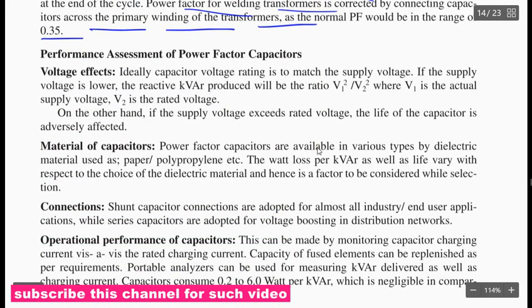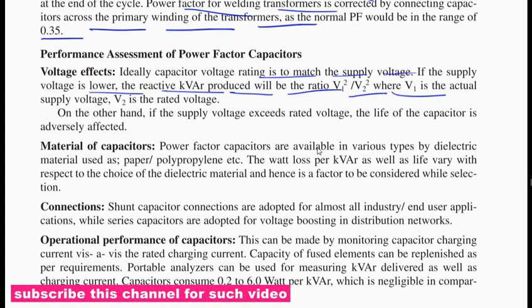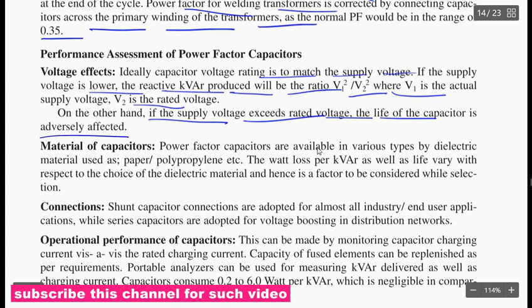Performance assessment of power factor capacitor. Voltage effect. Ideally, the capacitor voltage rating is the same as the capacitor supply voltage. If the supply voltage is lower, the reactive kVAR produced will be in the ratio of V1 squared divided by V2 squared, where V1 is the actual supply voltage and V2 is the rated voltage. On the other hand, if the supply voltage exceeds the rated voltage, the life of the capacitor is adversely affected.